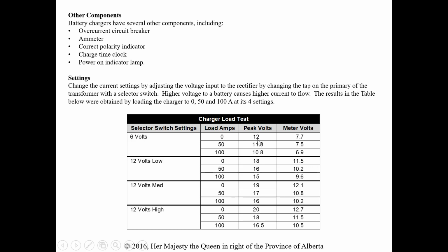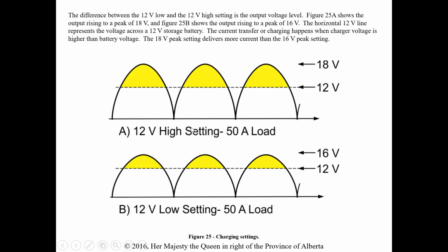Now they say the voltage change, we'll talk about coming up here, is basically because of the volt drop across the PN junction of the diodes. So that's what you're seeing change as we start loading this up. The current is increasing, so the I squared R losses in the windings too would potentially create a volt drop, but they said it's mainly the PN junction, the volt drop across the diodes. Okay, so this kind of shows what's happening when it's charging, and the amount of current going through there is based on the difference between the charging voltage and the actual battery voltage. So they're using the 12 volt high setting at 50 amp and 12 volt low.